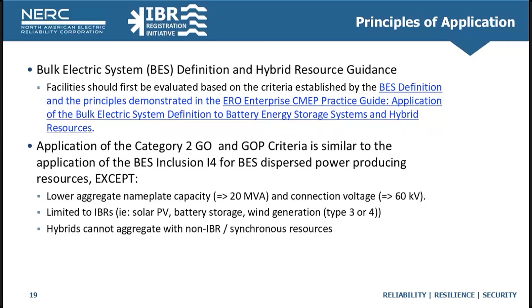Key points to remember when applying the Category 2 criteria: non-BES IBRs are connected at a common point of connection at 60 kV and above, a change from the 100 kV threshold associated with the BES definition. Aggregate nameplate capacity is the apparent power rating in MVA and is calculated using the apparent power rating of the individual inverters. This is key when calculating that aggregate nameplate capacity for meeting the thresholds within the registration criteria.